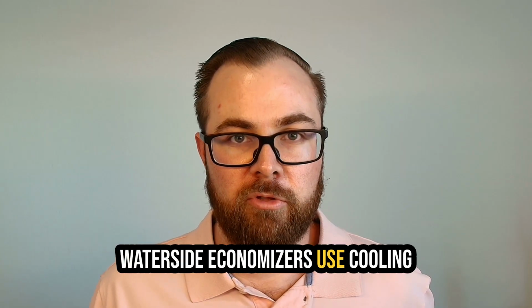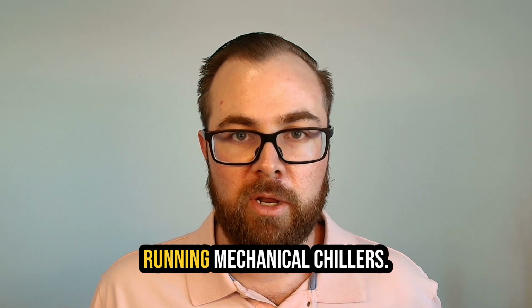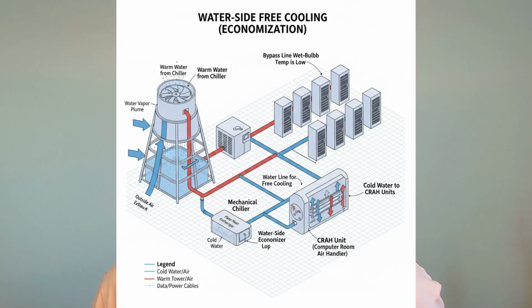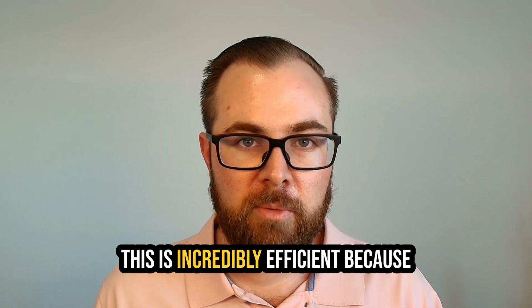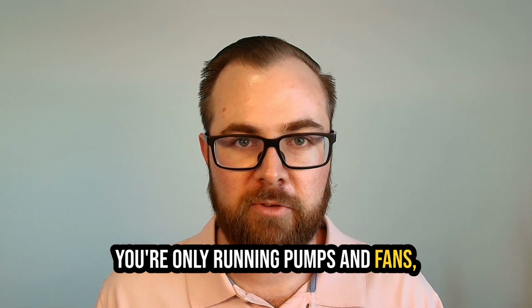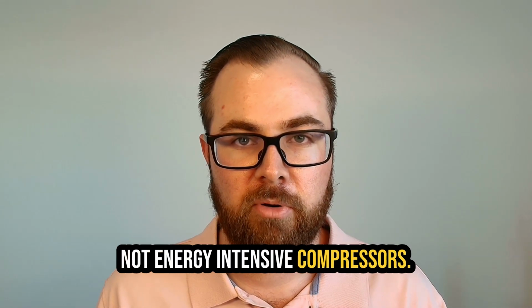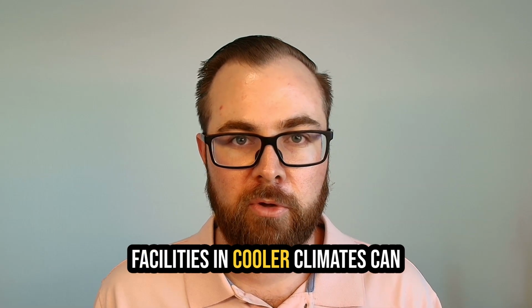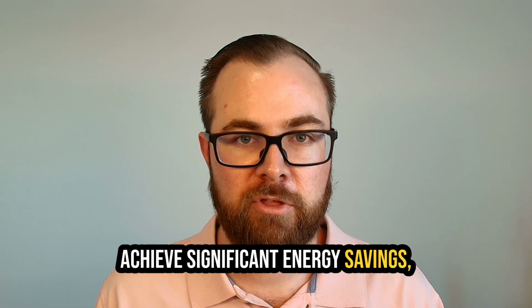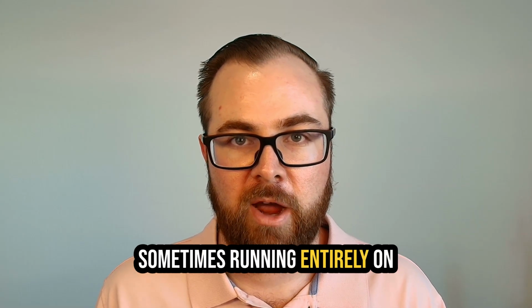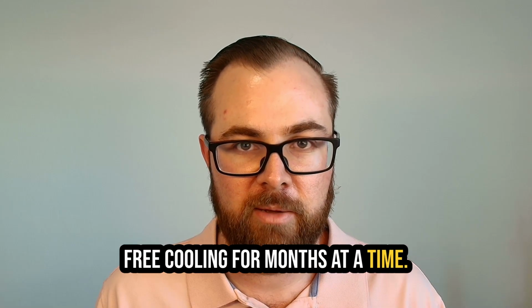Waterside economizers use cooling towers to chill water without running mechanical chillers. Cooling towers work through evaporative cooling. Water evaporates, absorbing heat and cooling the remaining water. When outdoor wet bulb temperatures are low enough, cooling towers alone can provide all the cooling you need. This is incredibly efficient because you're only running pumps and fans, not energy-intensive compressors. Facilities in cooler climates can achieve significant energy savings, sometimes running entirely on free cooling for months at a time.